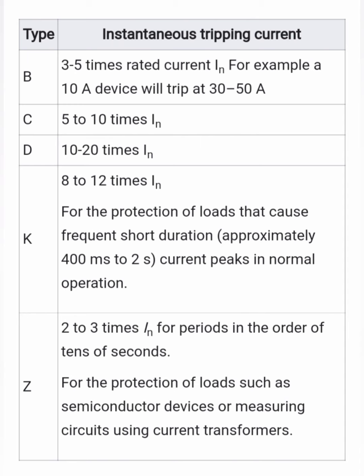For example, the MCB is 10 amps. B type MCB means it will withstand up to 3 to 5 times of your current. Then C type in the sense 5 to 10 times. Then D type in the sense 10 to 20 times. Next K type 8 to 12 times, for protection of loads that can cause frequent short duration current peaks in normal operation. Then Z type 2 to 3 times for a period in the order of tens of seconds. So these are all the types of MCBs used.